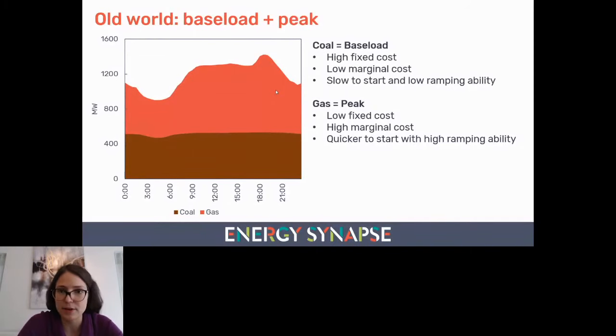Now, of course, there are variations in these categories. For example, black coal tends to be a fair bit more flexible than brown coal, and even in the gas world, things like fast-start and open-cycle turbines tend to be more flexible than closed-cycle turbines. But the main message I want to get across is that this paradigm we used to have, baseload plus peak, comes from the economic characteristics of these traditional generators. It isn't actually a technical requirement in the grid.